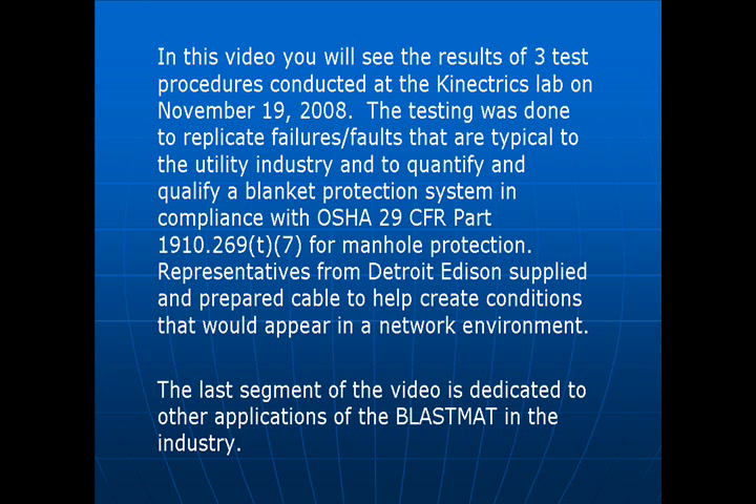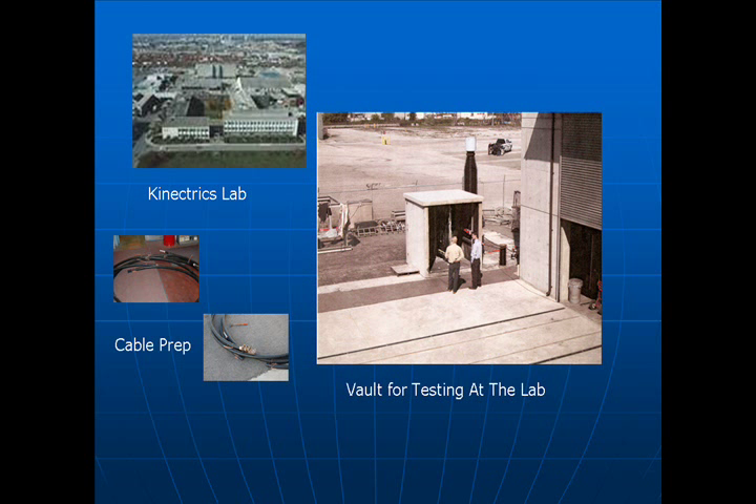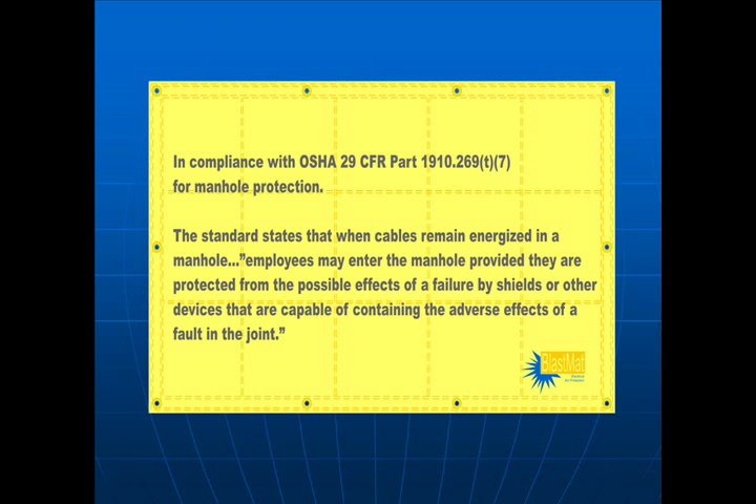In this video you will see the results of three test procedures conducted at Kinectrics Lab on November 19, 2008. The testing was done to replicate failures and faults that are typical to the utility industry and to quantify and qualify a blanket protection system in compliance with OSHA 29 CFR Part 1910-269-T7 for manhole protection. Representatives from Detroit Edison supplied and prepared cable to help create conditions that would appear in a networked environment. The last segment of this video is dedicated to other applications of the blast mat in the industry.